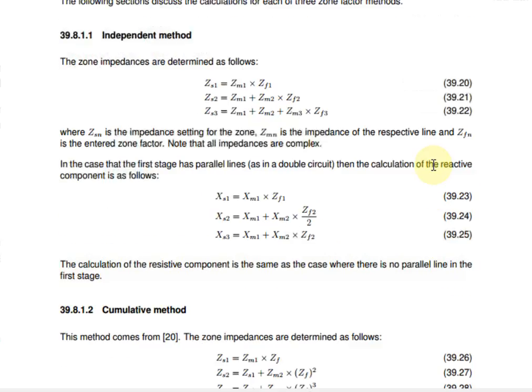Here you can see the independent method. ZM1, ZM2 and ZM3 represent network impedances. ZF1, ZF2 and ZF3 represent zone factor settings. The zone factor settings are defined by the user in the coordination assistant. The calculated reach is ZS1 for zone 1, ZS2 for zone 2 and ZS3 for zone 3. You can see that there is a special consideration for parallel lines as well.